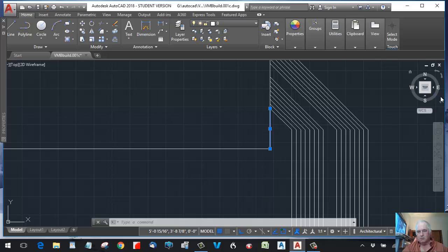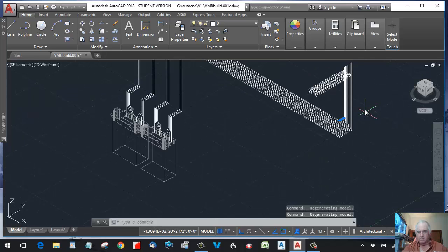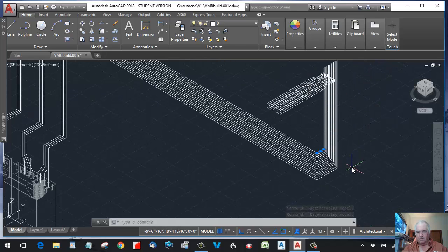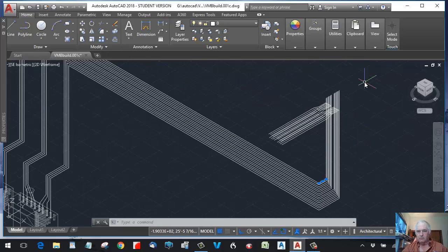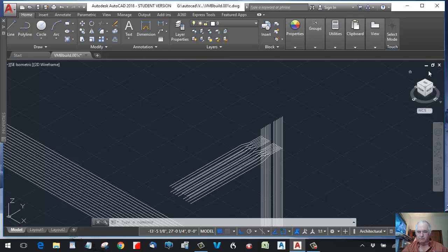And then let's take a look at how that plays out above. It goes up to the level of getting on the rack, and it's a little hard for you to see here, but this is the rack, top and bottom, 5/8 of an inch spread, and staggered slightly, and there's the gap in between for the sprinkler line.